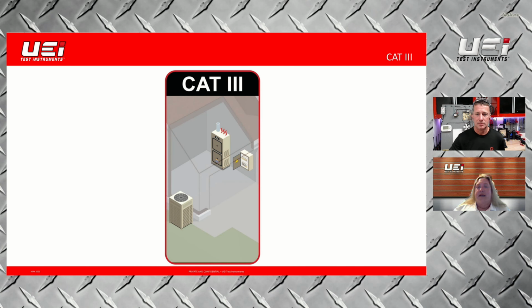So what's Category 3? Category 3 is really what we're going to be looking a lot at. Category 3 is from that control box, your control panel, to the outlet or to the hardwired appliance. So when we're looking at our AC systems, our furnaces, those are generally going to be in your Category 3 - everything that is hardwired and/or from the box to the outlet, everything in between those. So we really need to have a Category 3 or higher rated meter in the HVAC industry.